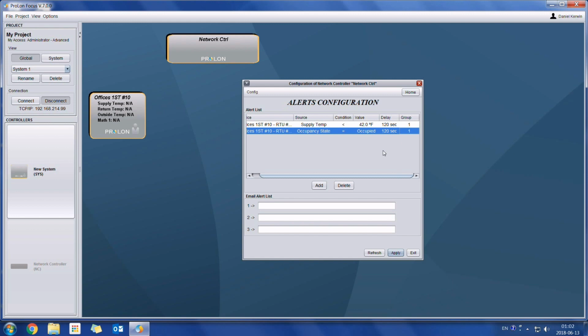What that does is that the email will only be sent off once all conditions of group 1 have come to pass. So in this example, the email will only be sent if the unit is occupied and the supply temperature gets colder than 42 degrees. If ever the unit is unoccupied, so during nighttime, then we would not get that email alert. So what this allows us to do is not simply be alerted due to a specific point, but really looking at that point in a context as well.